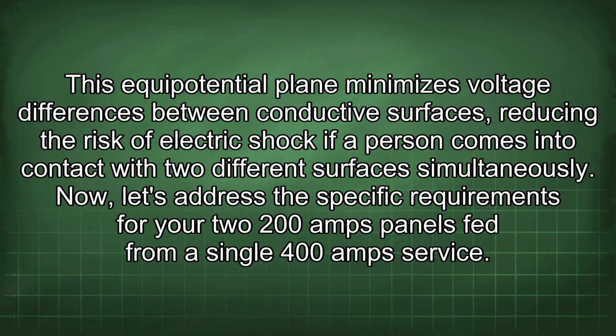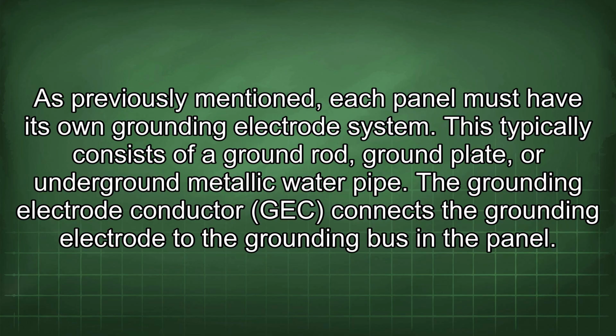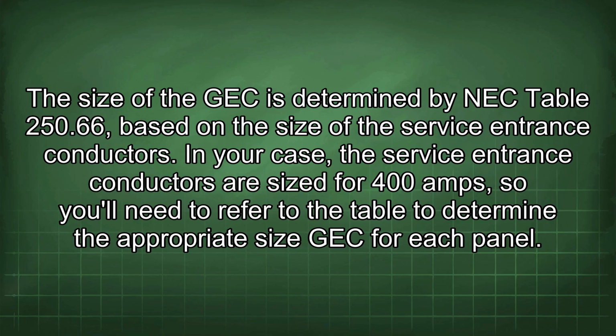Now, let's address the specific requirements for your two 200 amp panels fed from a single 400 amp service. As previously mentioned, each panel must have its own grounding electrode system. This typically consists of a ground rod, ground plate, or underground metallic water pipe. The grounding electrode conductor, GEC, connects the grounding electrode to the grounding bus in the panel. The size of the GEC is determined by NEC table 250.66 based on the size of the service entrance conductors. In your case, the service entrance conductors are sized for 400 amps, so you'll need to refer to the table to determine the appropriate size GEC for each panel.